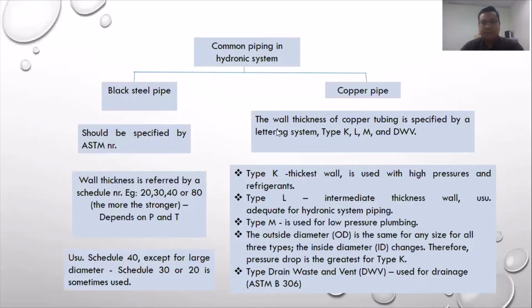So we go to the copper pipe. The wall thickness of copper tubing is specified by a lettering system: type K, L, M, and DWV, which is drain, waste, and vent. So it is a different type from the black steel in the selection system. Type K, the thickest wall, is used with high pressure and refrigerant. Type L, intermediate thickness wall, is usually required for hydronic system piping. And type M is used for low pressure plumbing.